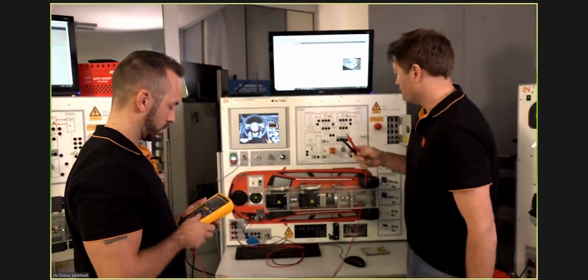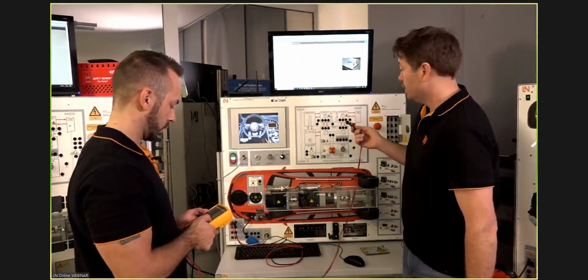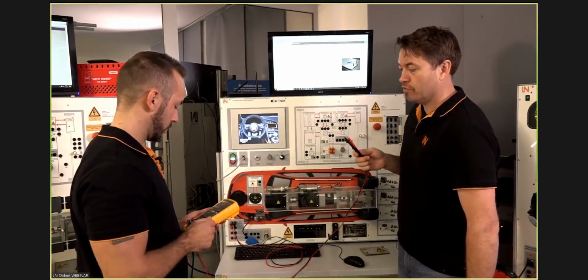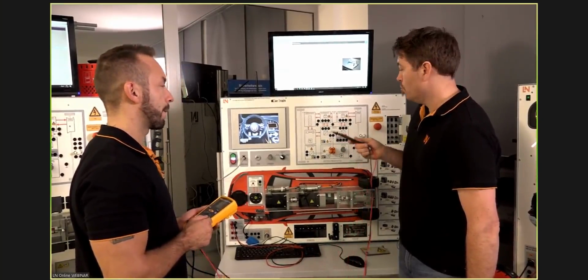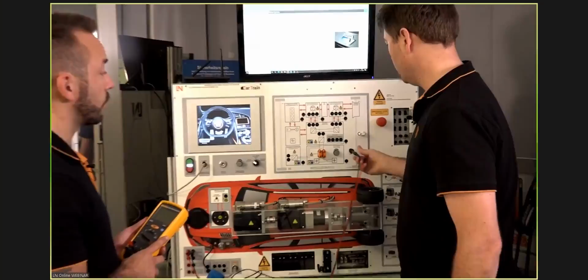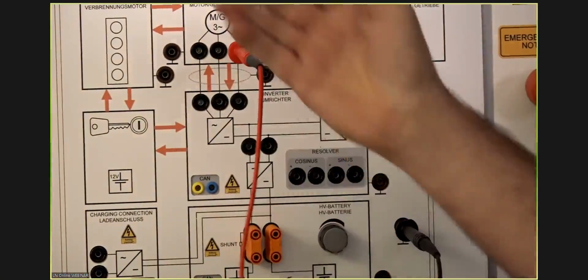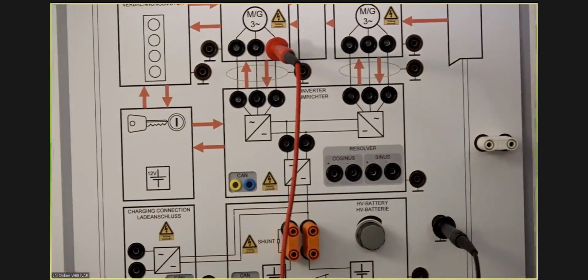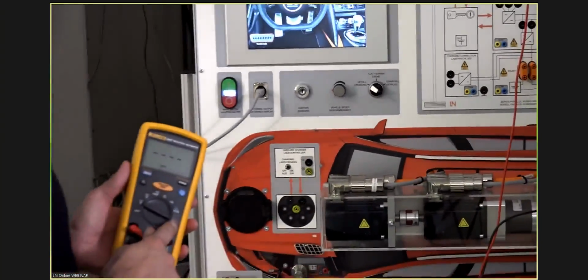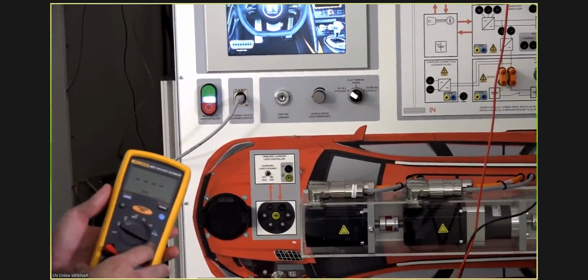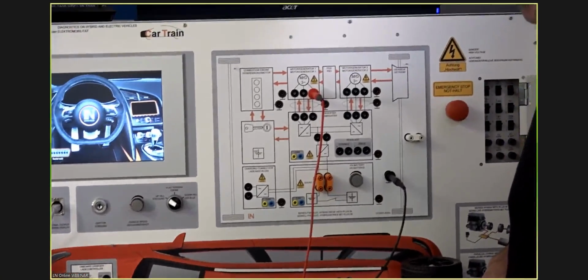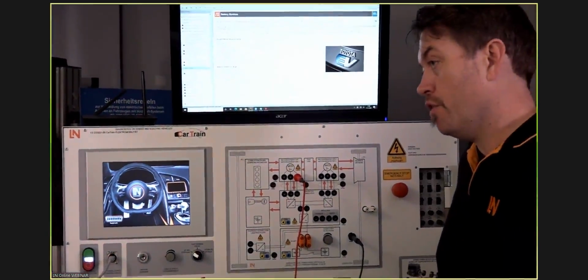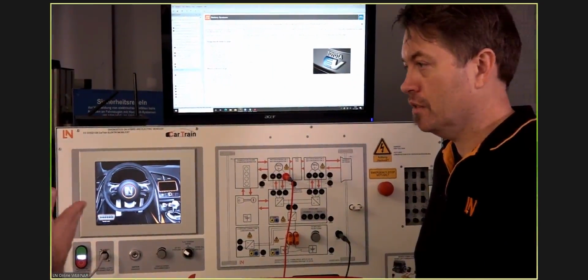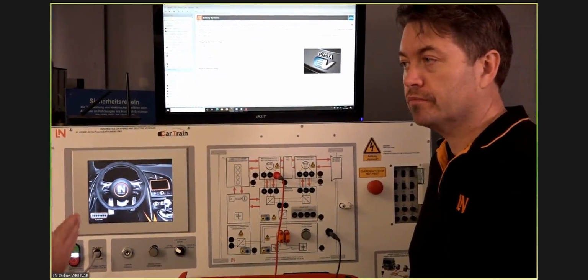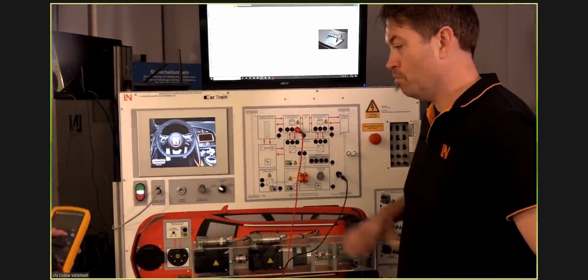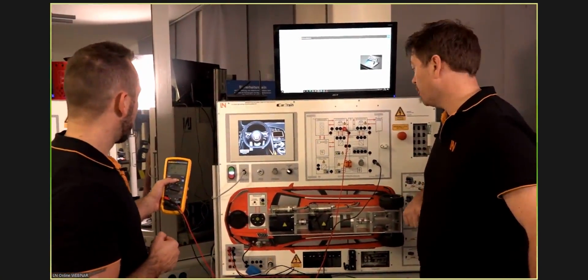So what we can do here, for example, is go along with a normal multimeter, test this, and we'll see, okay, we're not seeing any resistance faults whatsoever. But what we can do now is go to ground and, for example, go over to, it just said MG. Another question: when we have different voltages which we can choose, which one should we use, or how do we know which voltage we should use for our high voltage system? You should always read what the manufacturer says. Okay. Some specify 500 volts, some say 1,000 volts is okay. At this system, we know that we have a maximum voltage of 300 volts, so we are fine with 500 volts. Yep. Okay, cool. Also fine with 1,000 volts if we need to. Absolutely.